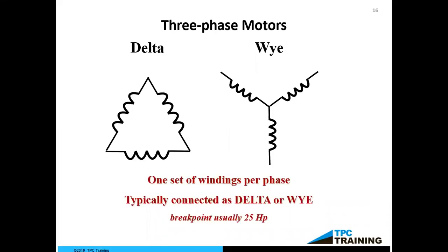Three-phase motors can be wound in a couple of different ways. One, it could be wound as you see on the left, which is a delta configuration. In that configuration, we would make it look like a triangle, just like it does right here. But that delta gives us more torque on startup. So if I had a very large motor and it was very difficult to start because of the load we connected to it, then I would want that motor wound in a delta configuration.